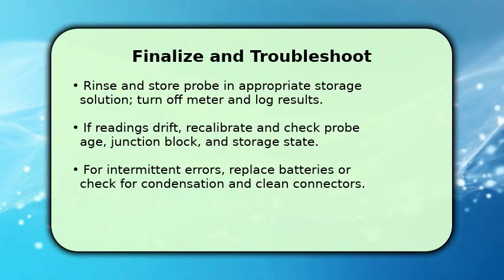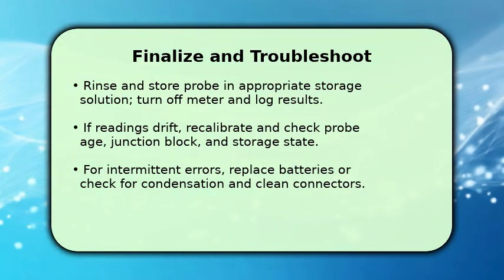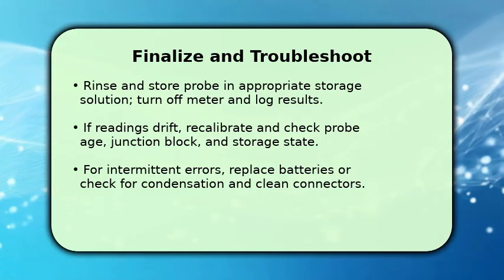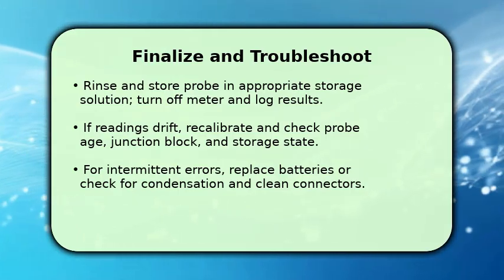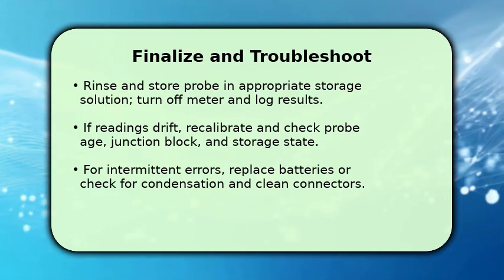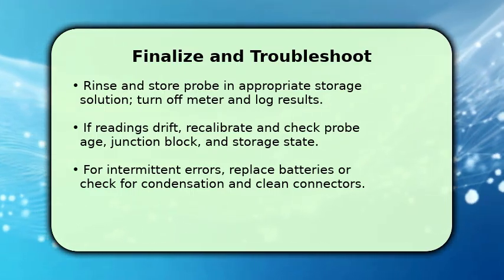Finish by properly storing the probe and documenting your measurements so they remain valid. After each session, rinse the probe, place it in the recommended storage solution, and power down the meter. Log the pH, temperature, and any anomalies.